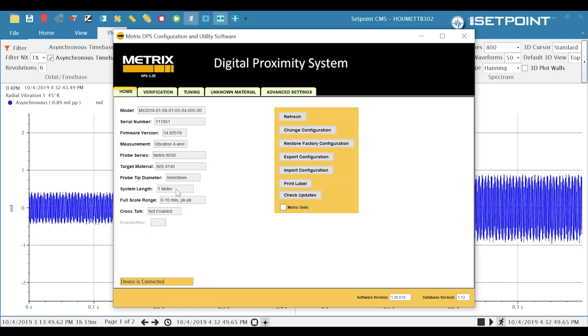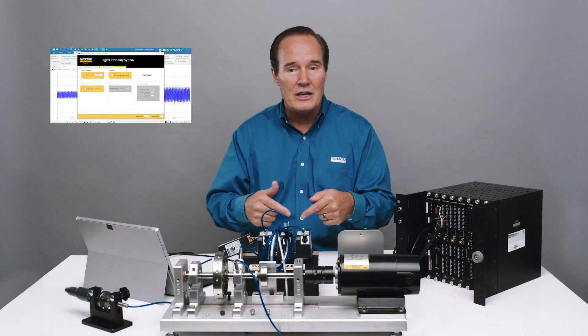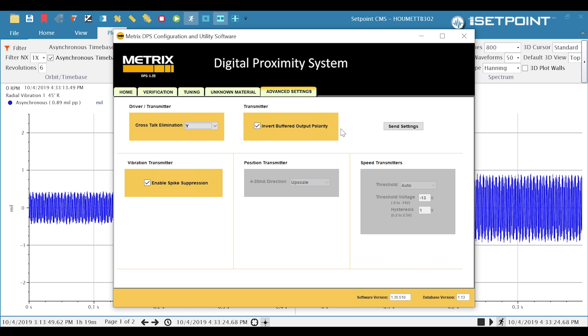Before this setup, instead of having the traditional five meter systems, I took out the extension cables and reconfigured everything for a one meter system to make things cleaner. So now we'll go to the advanced settings and change the frequency of the transmitter to Y. You can do the same thing with the driver. So if you had our MX8030 probes with MX2034 transmitters or MX2033 drivers and you had crosstalk, you can eliminate it — it works with either one. Let's go ahead and change it to Y and click OK. Right as it updates, you'll start to see a change in the set point system, because it's going to sense that we no longer have the crosstalk problem since we've shifted the frequency.